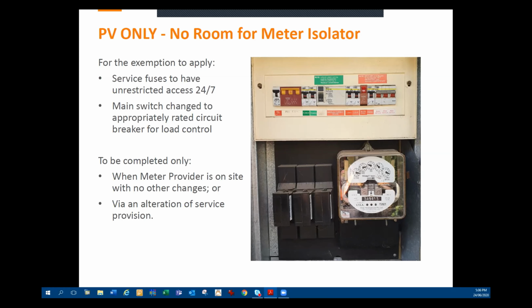For another one where there's no room for a meter isolator and there's no main switch, again the service fuses must have unrestricted access 24/7, and an alteration of service request is to be raised. And the main switch needs to be installed as a meter isolator, so that can be added. There may be cases where we can look at other alternatives, but the first thing for something like this is that there's no single main switch. Every circuit breaker on there is basically a main switch, so a separate main switch has to be installed, whether that's directly before the meter as a meter isolator, or if we need to have a closer look at the job and apply a further exemption from there.